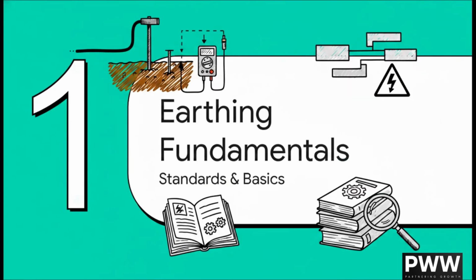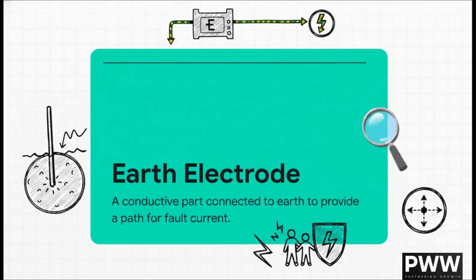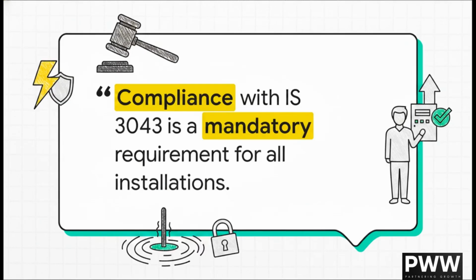Any good field manual has to start with clear definitions, right? So think of an earth electrode kind of like an emergency exit for electricity. Our sources define it quite simply. It's a conductive part intentionally connected to the general mass of the earth, and its primary job? To provide a reliable, low-impedance path for fault current to safely leave the installation and get back to the source. It is all about protective equipotential bonding. By connecting non-current-carrying metalworks to this earth, we limit their potential during a fault, which is exactly what prevents dangerous, life-threatening shocks.